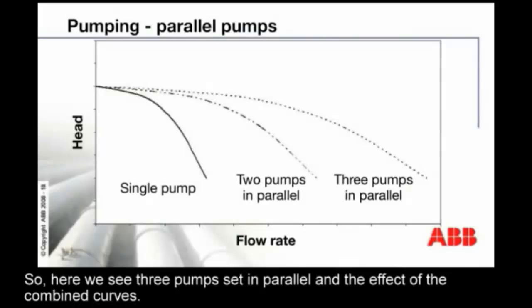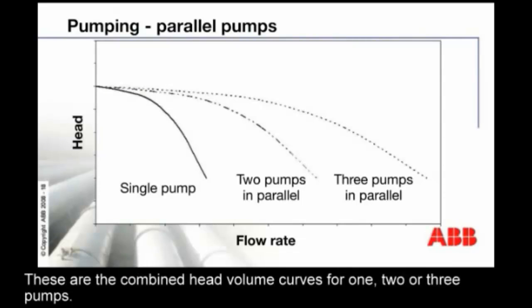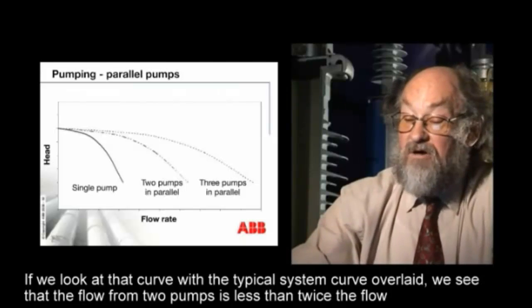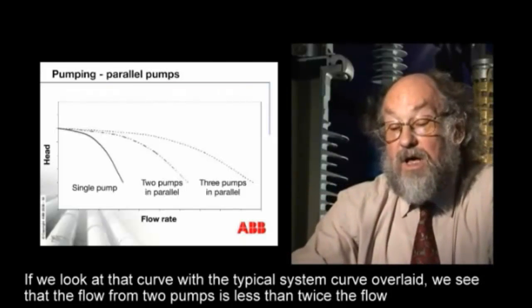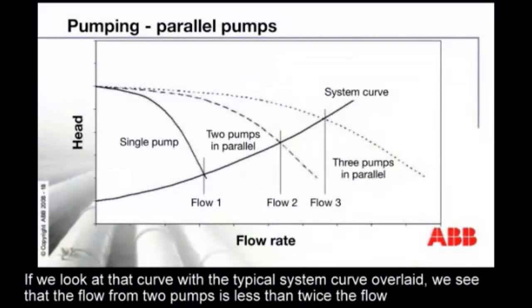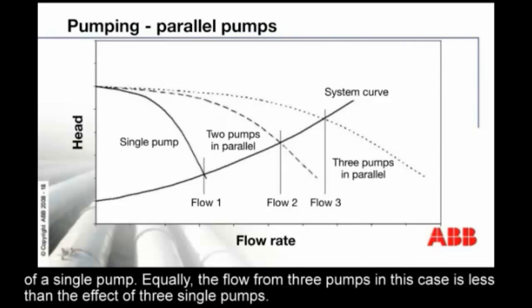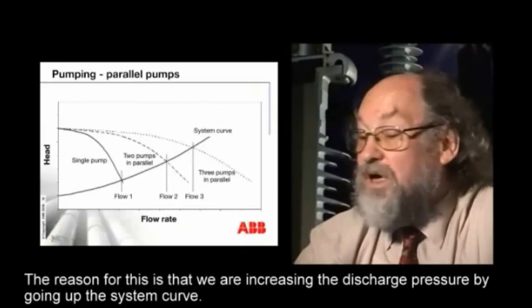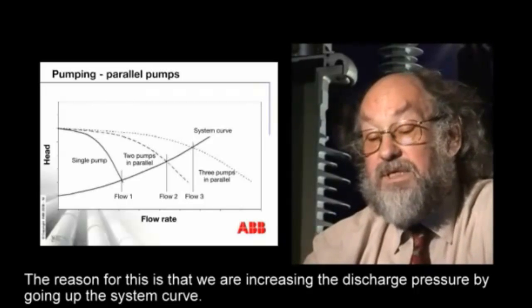Here we see three pumps set in parallel and the effect of the combined curves. These are the combined head-volume curves for one, two, or three pumps. If we look at that curve with a typical system curve overlaid, you'll see that the flow from two pumps is less than twice the flow of a single pump. Equally, the flow from three pumps is less than the effect of three single pumps. The reason for this is that we're increasing the discharge pressure — they're going up the system curve.